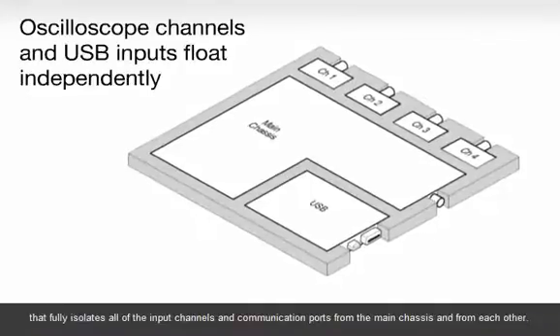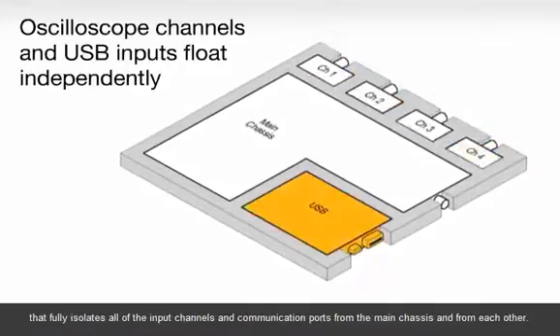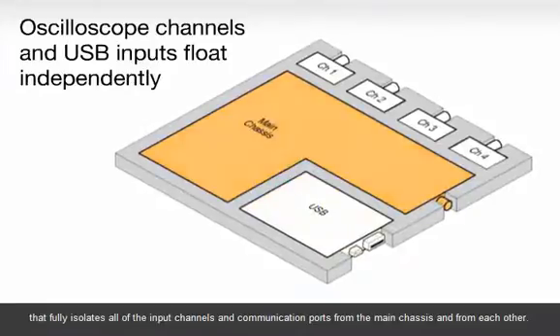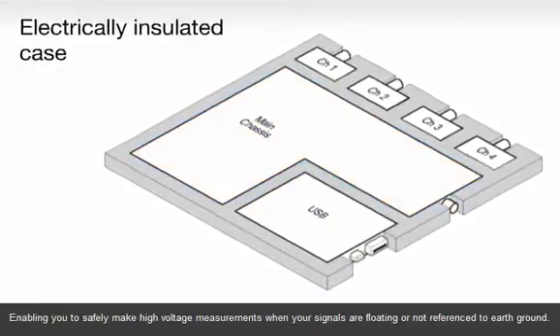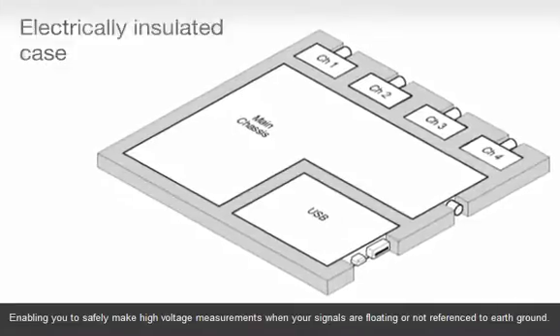that fully isolates all of the input channels and communication ports from the main chassis and from each other, enabling you to safely make high-voltage measurements when your signals are floating or not referenced to earth ground.